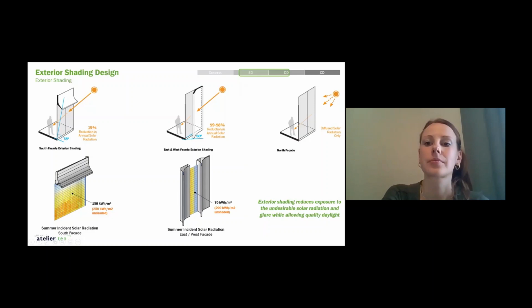And then the north facade really doesn't need any exterior shading for solar radiation. It still has some diffuse solar radiation, and may have overlit conditions or glare because of the brightness of the sky. So for that facade, we strongly recommended automated shades. Automated shades can really save energy for the building if you have long-term exposure to overlit conditions or glare, so people who sit on the perimeter won't just draw the blinds down and keep them like that the whole day. They're more responsive to the outside - they open them when possible and close them when conditions require it. So that was our only recommendation for the north facade. Otherwise, there was no concern about the solar radiation.